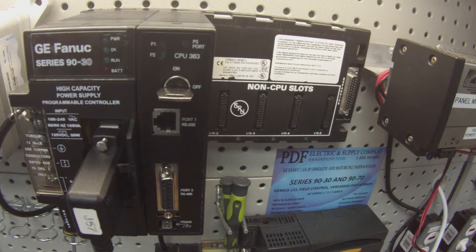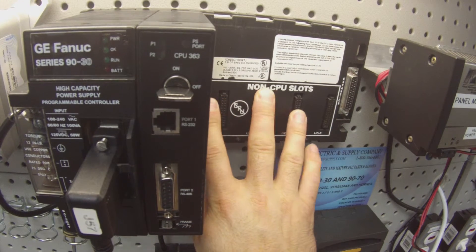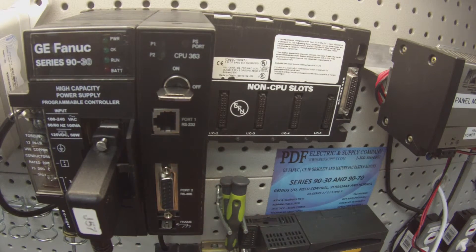Hello and welcome to PDFsupply.com. Today we're going to be testing a 90-30 processor. I have here an IC693CPU363 and I have it attached to an IC693CHS397 slot rack which is empty. Slots 2 through 5 need to be empty for this test. It's just a simple test on the processor and it's being powered by a high capacity power supply, the IC693PWR330.